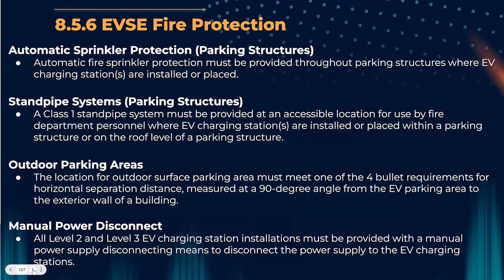If you're installing EVSE in a parking structure, it'll need to have automatic sprinkler protection throughout and have Class 1 standpipe for the fire department.